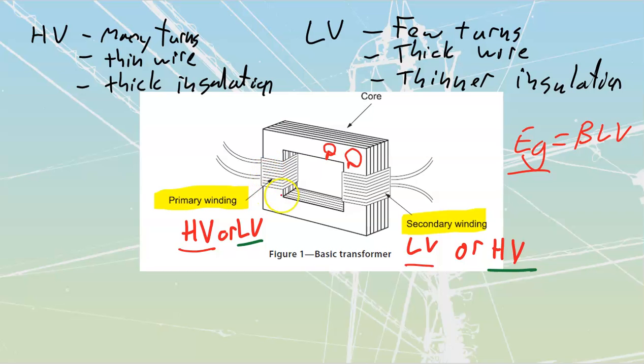Usually what's actually happening inside of our transformers is you're going to see welded joints in a lot of your transformers, where they would have created this winding just as a loop off of a machine. Build it as a loop. They'll just run it as a loop around a square form, and then all they do is take this, which would be formed like a C shape in a flat bar, and shove that through there, and then they weld across the bottom. That's why you're going to see those joints across there.